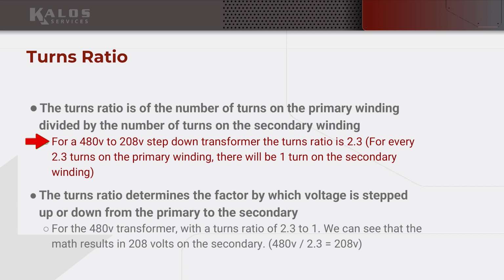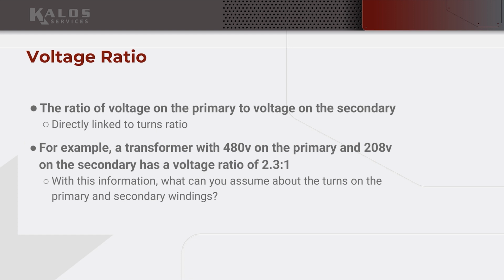If we wanted 240 volts, it would be 2, right? 480 volts divided by 2, you'd have 240 volts on the secondary, which makes me stop and wonder why we don't just create 240 volt secondaries. Probably where we're going to figure it out is because you wouldn't get 120 volts at your center tap, and that would be a problem. So it's a trade-off.